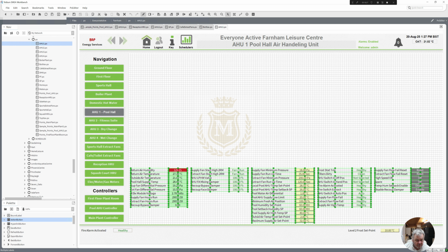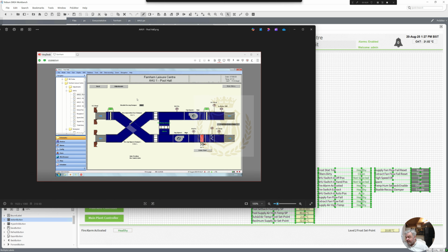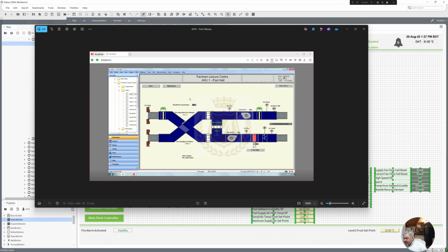And my pool graphic, which I've actually got a copy of, someone took a snapshot a long time ago, well, 7th of the 8th to be precise, because that's a snapshot there, 7th of the 8th, time 7:31. Outside air was 11.8 degrees. So we've got some brick walls there, so that's my outside air going in. That is totally different temperature to what that is. But I did notice that on the points as I was going through. Let me show you what I mean.